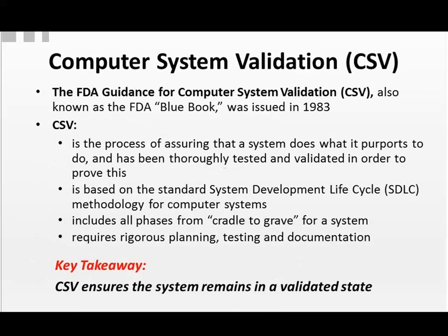Computer system validation started up with FDA in 1983 with the Blue Book. Basically, they said that it's the process of assuring a system does what it purports to do, that you've defined those requirements and you've thoroughly tested and validated to prove that every single requirement works. It's based on the System Development Life Cycle methodology, the SDLC. It includes every phase from cradle to grave for a system. And as you can see, it requires rigorous planning, testing, and documentation throughout.